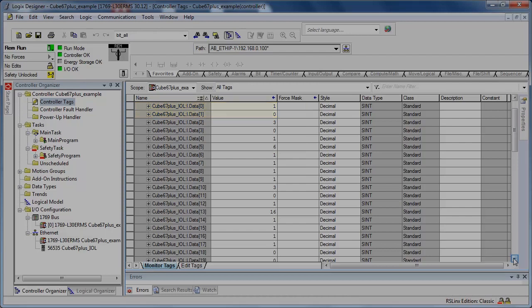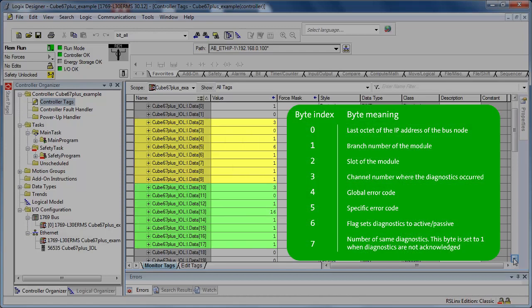The diagnostic data for the IO modules are transmitted by the virtual diagnostics module. They start at the input data by 2. Now every diagnostic message is composed by 8 bytes. Bytes 2 to 9 contain the first diagnostic message and bytes 10 to 17 the second message.